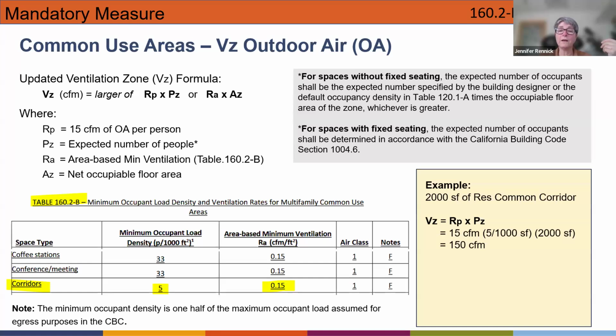first part of the formula and plug in your 5 per 1,000 square feet. You end up with 150 CFM, or you do the second part of the formula, which is the 0.15 CFM per square foot, but you have 2,000 square feet of it. So 300 CFM, and then you pick the larger of the two, and then you can pick your ventilation system to meet the 300 CFM requirement.